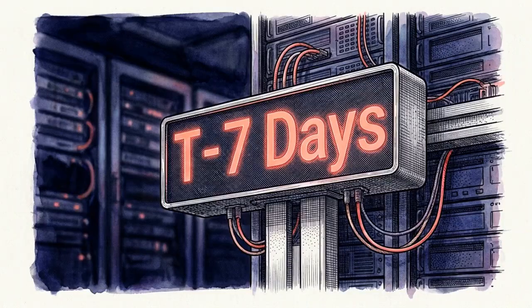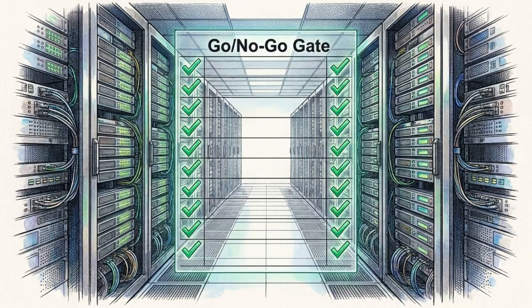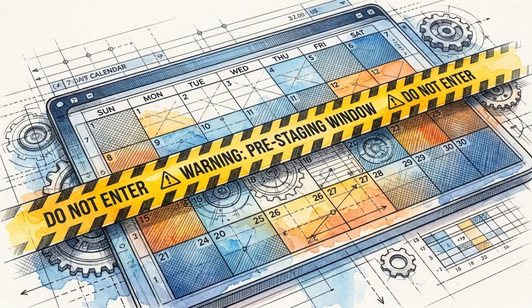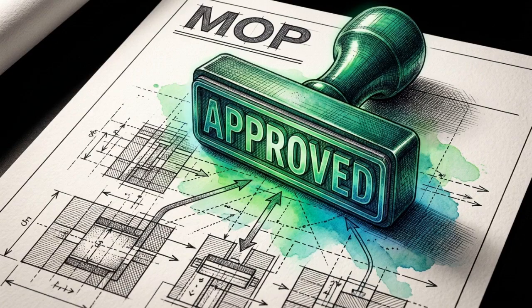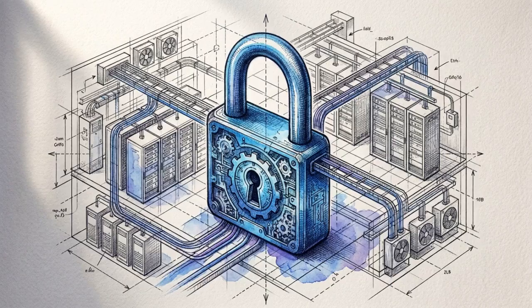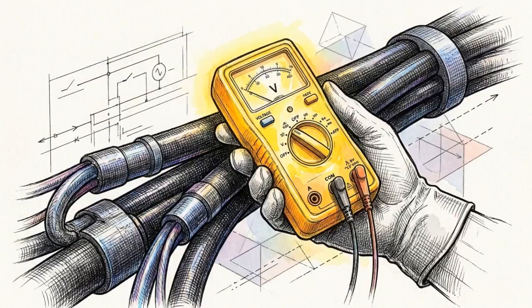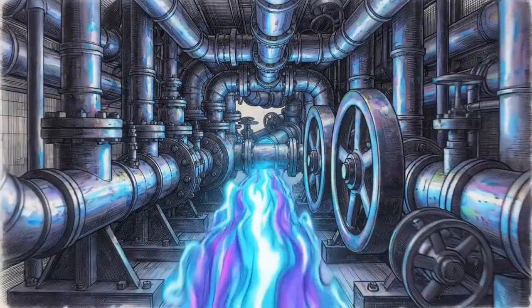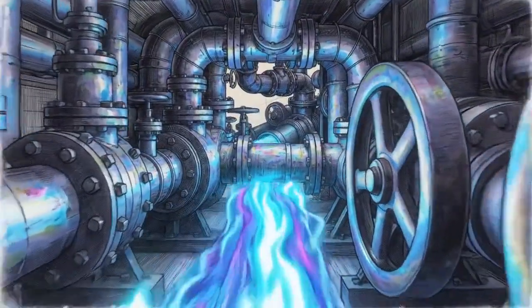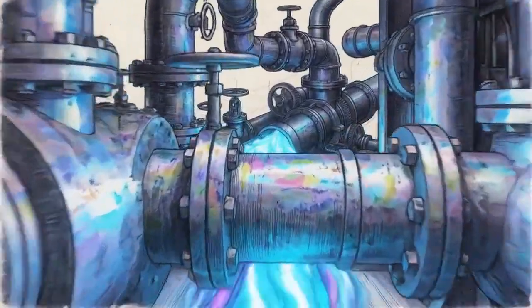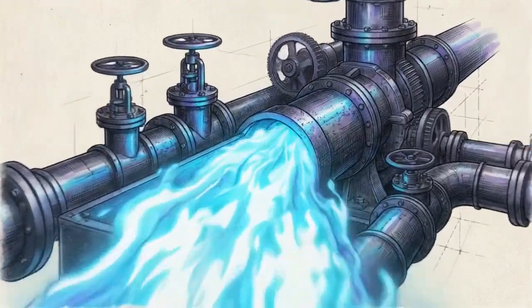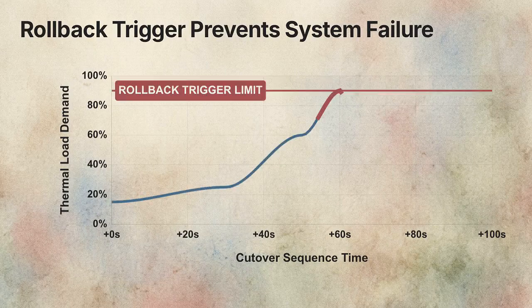The ultimate stress test for this governance framework occurs during a controlled cutover. Executing high-risk mechanical changes on a live, active data center without dropping the IT load is a zero-tolerance maneuver. The days leading up to the change require strict pre-staging. Teams secure method of procedure approvals, issue facility-wide change freezes, and physically verify backup paths. Then comes 0 hour. The plant transitions from a protected pre-staged environment to active integration. Live data suddenly hits the modified mechanical loop. At this exact moment, strict rollback triggers dictate survival.